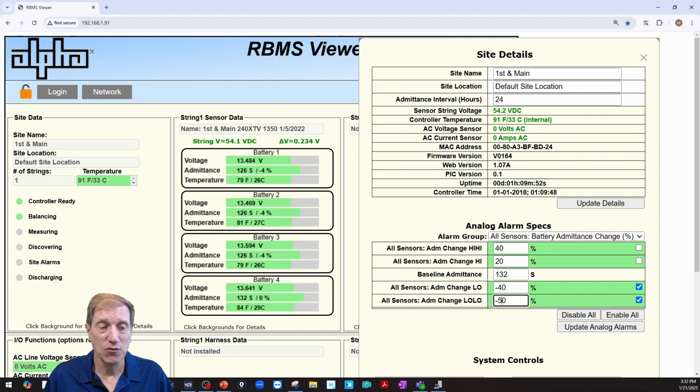So at 40%, it's really just a notification, okay? To tell you, hey, I'm aging, keep an eye on me, and maybe a few years down the road you might need to make a change then. So just kind of the first marker, okay? But if all of the other batteries are nowhere near that, that's another indication. I'll talk about that in a minute.